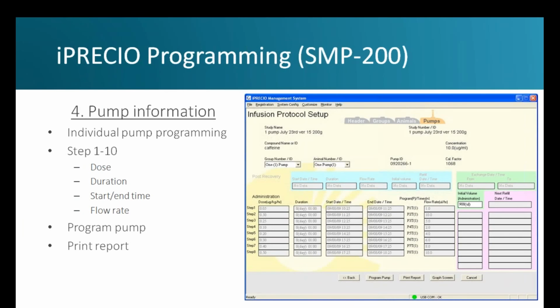It's worth mentioning that up to 10 flow rate steps can be programmed in variable infusion mode. And even further sophistication can be obtained by also using a repeat mode, where 10 steps can be programmed within up to 5 repeat cycle loops, and each loop may be repeated 250 times. Therefore, the iPRECIO pump is capable of programming extremely complex dosing parameters, and in many cases the capability would not even be fully utilized for most dosing studies.